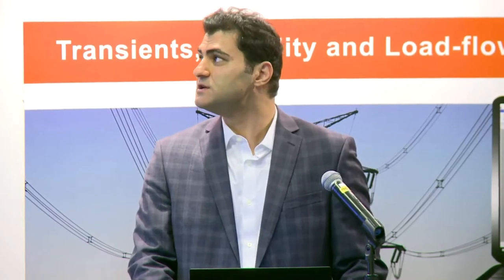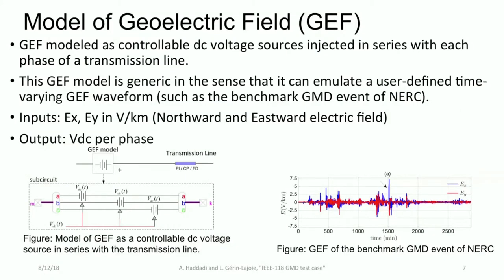To run GMD simulations in EMTP, we first need to model the geo-electric field — the DC voltages induced on transmission lines due to the magnetic field. In EMTP, we are able to model a user-defined time-varying GEF waveform. In other packages, you can only model a DC constant geo-electric field, but here we are not bound by that. For example, here is the GEF waveform of the NERC benchmark GMD event, which is highly time-varying.